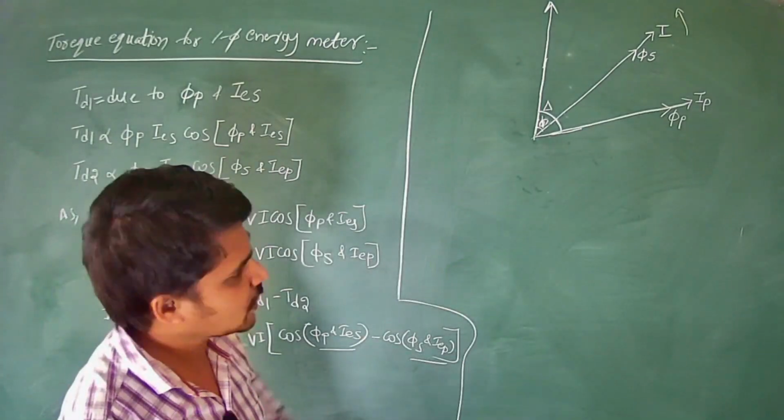Now, here, whenever the flux in the current coil changes, there is a rate of change of flux linkages, so an EMF is induced in the aluminum disc. That EMF we are calling the eddy EMF. This eddy EMF lags the current that is the cause of producing it, that is the current I, by exactly 90 degrees according to Lenz's law.